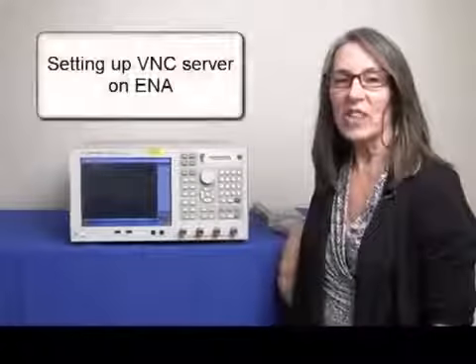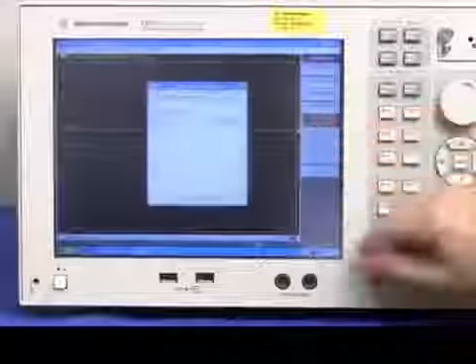Now I'd like to show you how to set up the VNC server on the network analyzer. First select the system key, then miscellaneous setup, then network setup, and finally VNC server configuration.